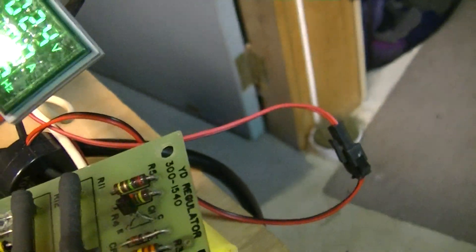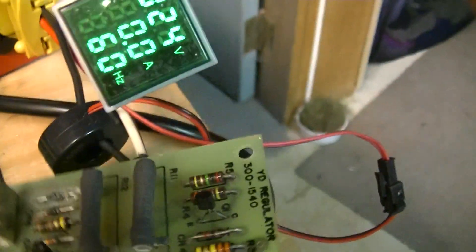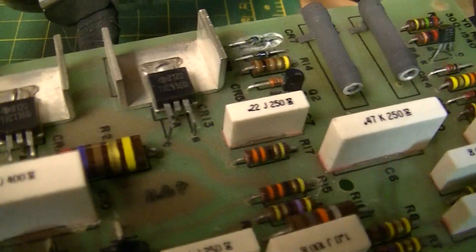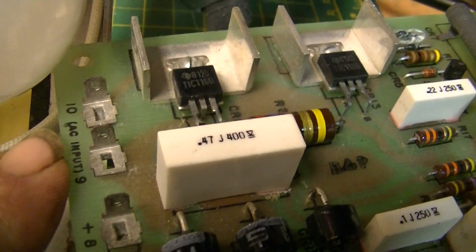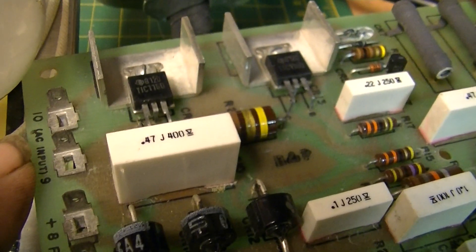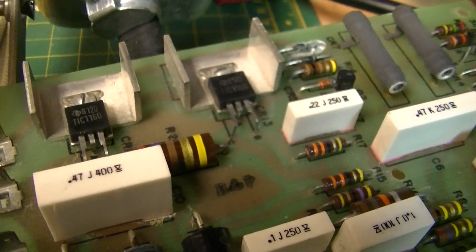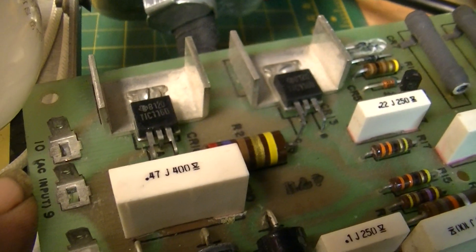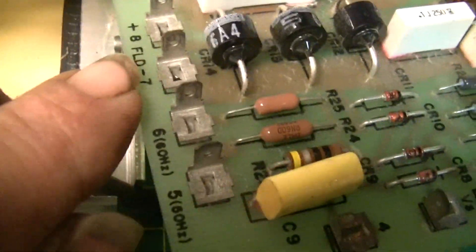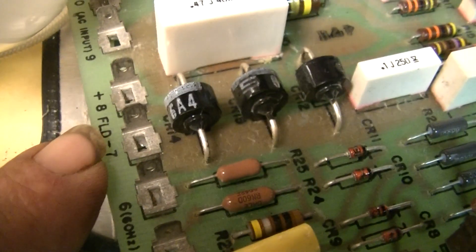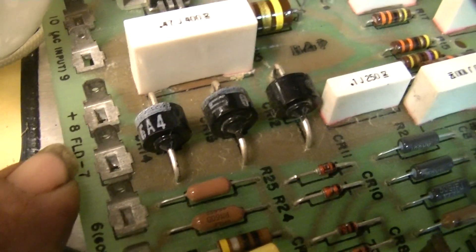When it's working, powering this light bulb, it'll drop about half an amp. This is AC input, these are sensing terminals, terminals 9 and 10. There's residual magnetism in the armature which will provide a small amount of voltage, perhaps 20 volts or something, and that will enable the board to excite itself. Then it'll put power out on the field terminals here, DC voltage, and that will build it up.